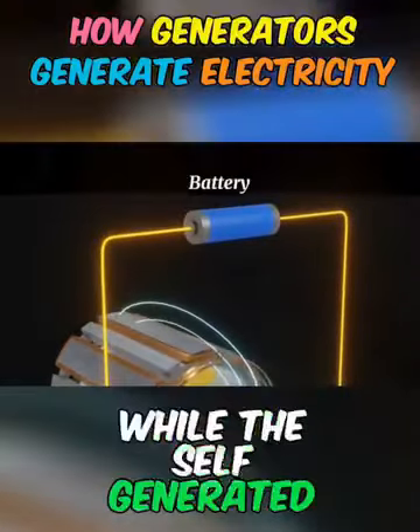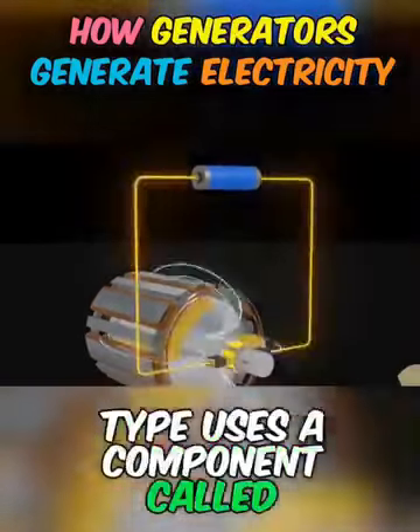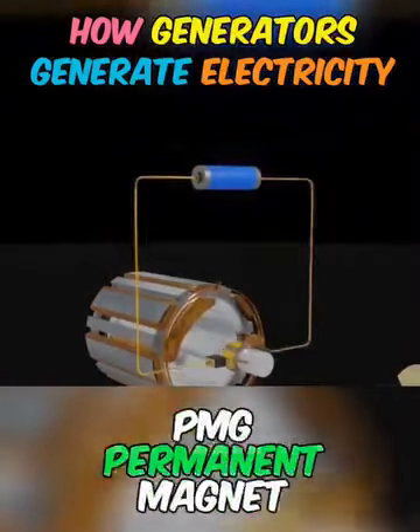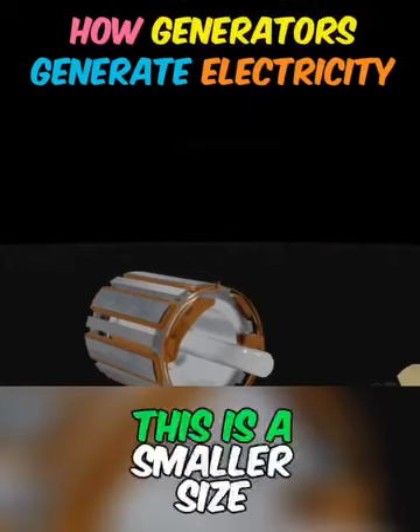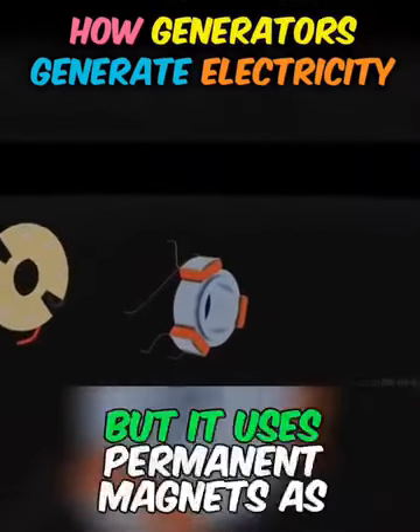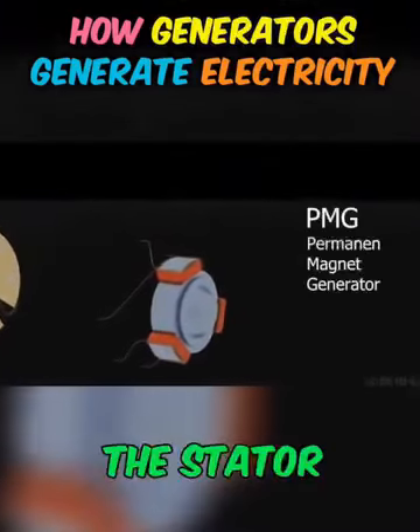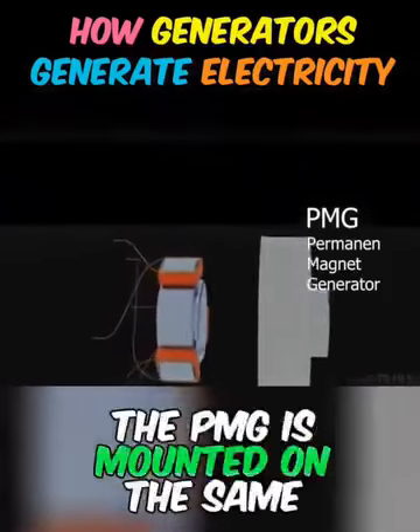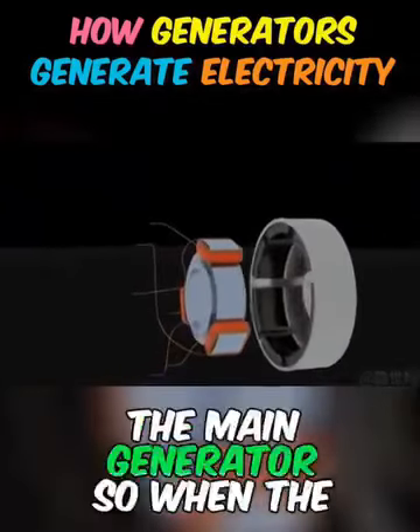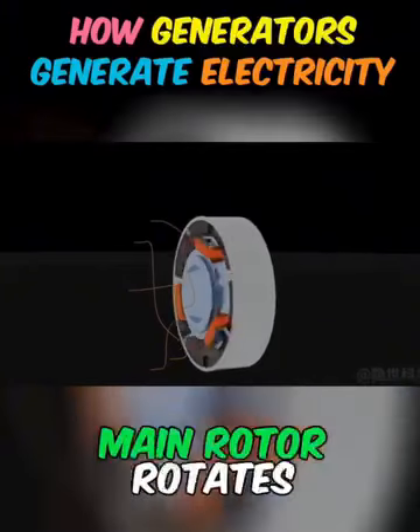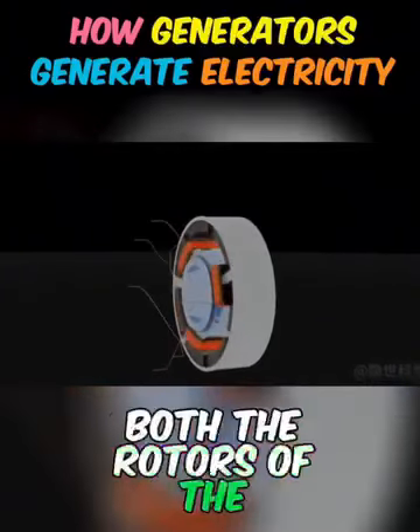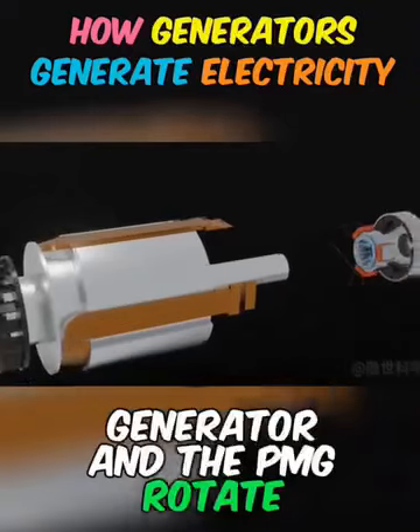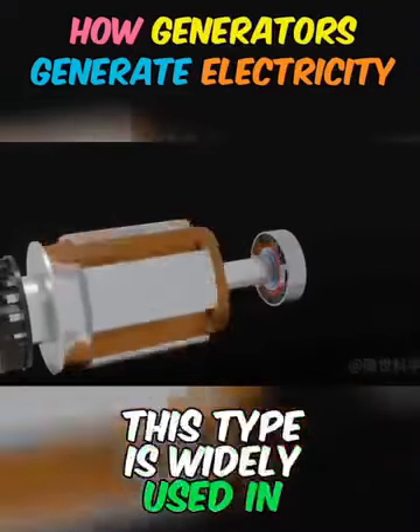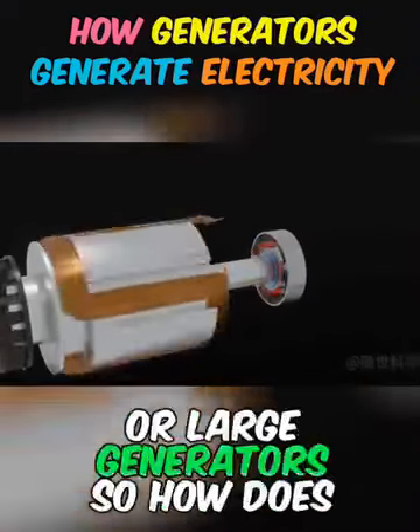While the self-generated type uses a component called PMG, permanent magnet generator. This is a smaller size generator, but it uses permanent magnets as the stator. The PMG is mounted on the same shaft as the main generator, so when the main rotor rotates, both the rotors of the generator and the PMG rotate. This type is widely used in generator sets or large generators.